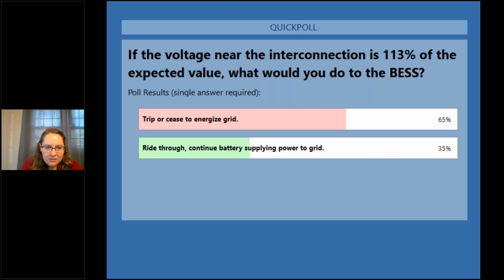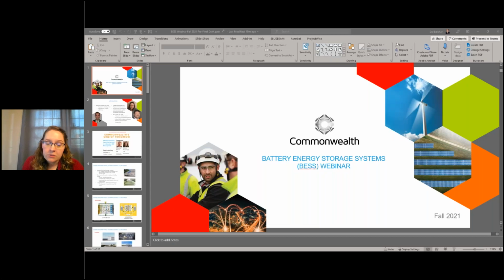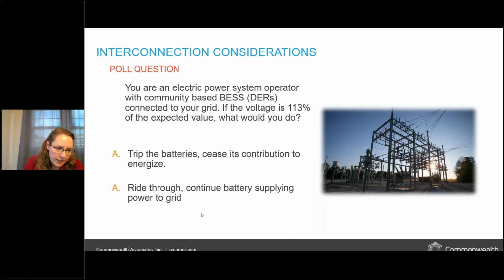Because of IEEE 1547, we have the ability to choose. So we see here about 65% of us think that 113% of voltage is too high, and we'd want to trip out and remove the batteries from the conversation. But 35% of us think, in our part of the power grid, we want to ride through. We want to see what these batteries can do. Maybe they can help stabilize that voltage somehow. So it's because of IEEE 1547 that we as the operators in this example would have the ability to make that decision on what's best for our local region, what's best for our local distribution grid.